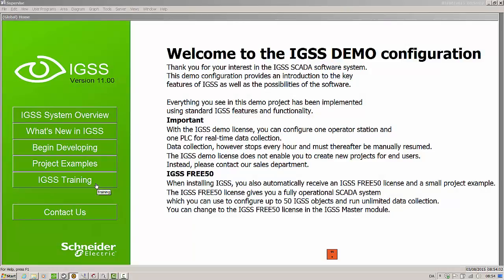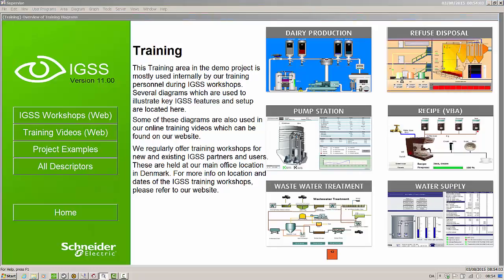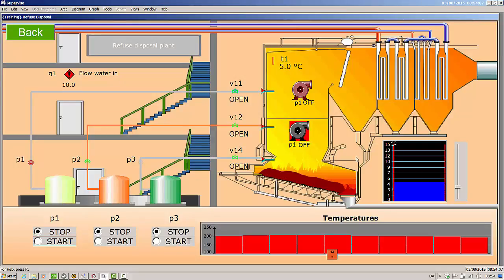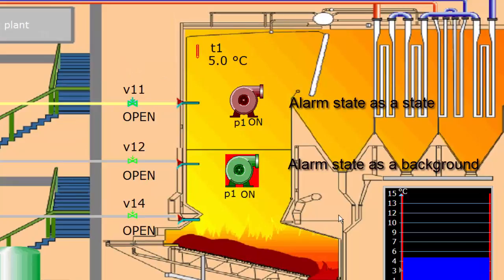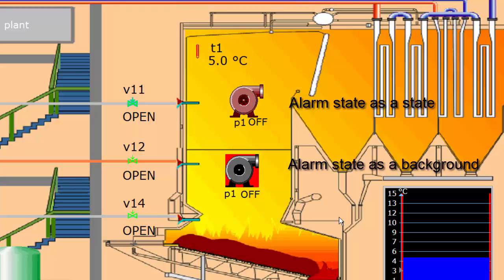The animated symbols have also been improved in IGSS 11. You can set an animated symbol to display alarms either as a state or in the background. Here, two pump animated symbols have been connected to the same P1 object. The symbols display the alarms in two different ways — one as a state and the other as a background. If you choose to depict alarms as a state, the alarm state will be displayed instead of the object state, meaning the object state cannot be seen. If you choose to depict alarms in the background, the animated symbol will still display the object state when the object is in alarm, and instead the background will be displayed with whatever properties have been defined for the alarm.